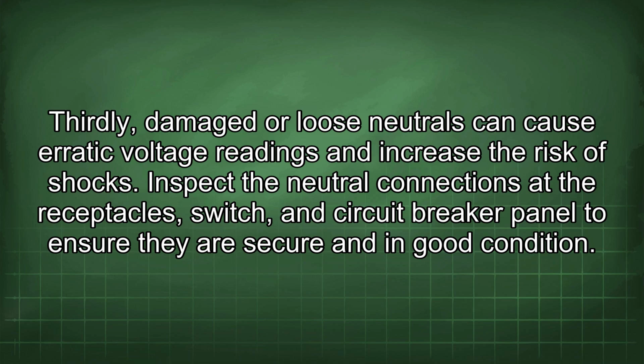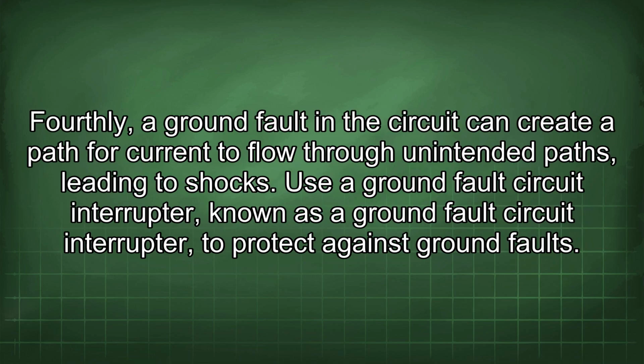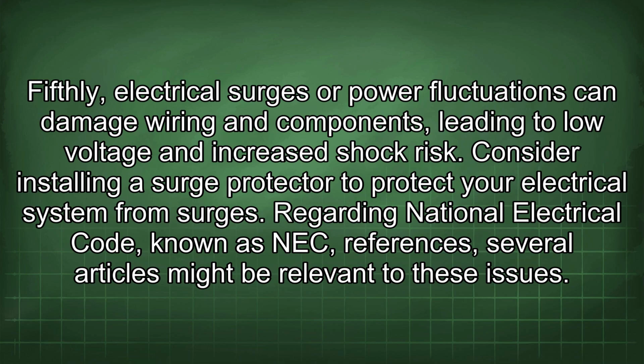Thirdly, damaged or loose neutrals can cause erratic voltage readings and increase the risk of shocks. Inspect the neutral connections at the receptacles, switch, and circuit breaker panel to ensure they are secure and in good condition. Fourthly, a ground fault in the circuit can create a path for current to flow through unintended paths, leading to shocks. Use a ground fault circuit interrupter to protect against ground faults. Fifthly, electrical surges or power fluctuations can damage wiring and components, leading to low voltage and increased shock risk. Consider installing a surge protector to protect your electrical system from surges.